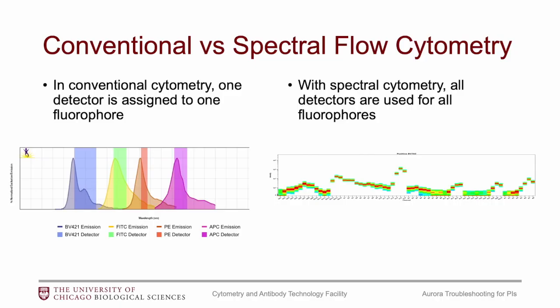To start out, I want to point out the main difference between conventional and spectral cytometry — mainly, it has to do with how the detectors are utilized. In conventional cytometry, one detector is assigned to one fluorophore. So in this spectra viewer here, the rectangle shows the detectors and the curves show the emission spectra for these four different fluorophores.